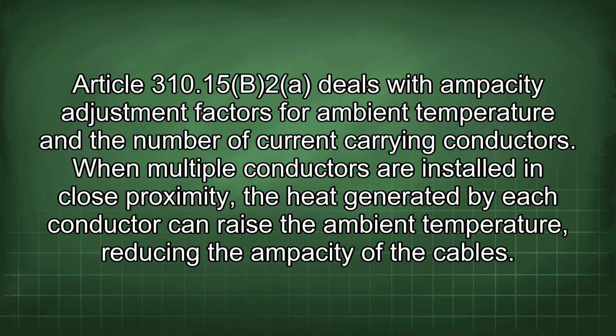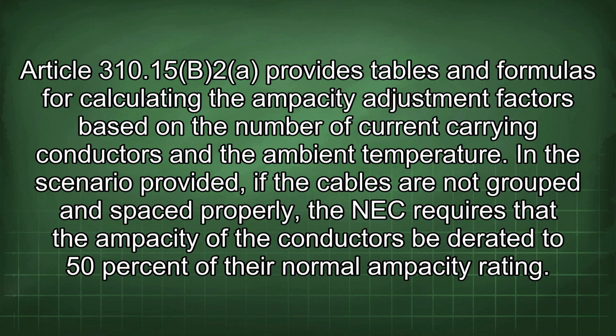Article 310.15b2 deals with ampacity adjustment factors for ambient temperature and the number of current carrying conductors. When multiple conductors are installed in close proximity, the heat generated by each conductor can raise the ambient temperature, reducing the ampacity of the cables. Article 310.15b2 provides tables and formulas for calculating the ampacity adjustment factors based on the number of current carrying conductors and the ambient temperature. In the scenario provided, if the cables are not grouped and spaced properly, the NEC requires that the ampacity of the conductors be derated to 50% of their normal ampacity rating.